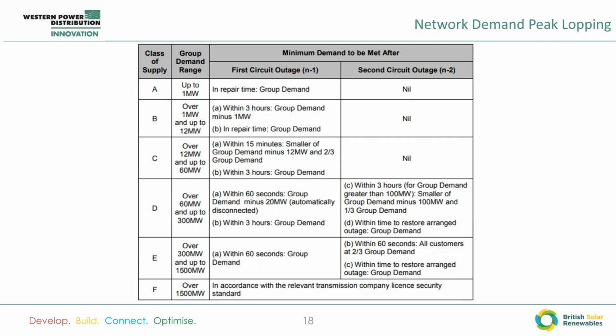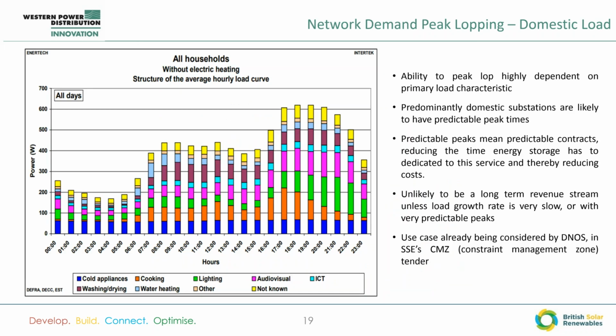Part of the issue of trying to avoid this reinforcement, though, is local networks don't follow national peak loads. What drives that big peak in the evening is domestic dwellings, because businesses often shut down at 5 or 5:30, everyone goes home, starts cooking and eating, etc. And the primary substation load characteristics depend heavily on what mix of loads they have connected. So if it's a mainly industrial area, there won't be the evening peak that you'd be expecting. It would actually decline, whereas a heavily residential area would have a much bigger peak during the evening.